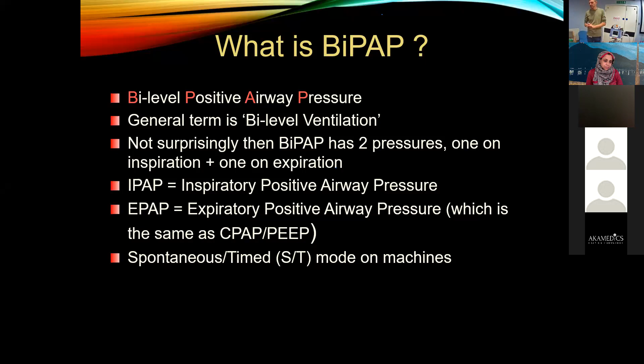So how does it work? The inspiratory phase pressure is triggered by the machine detecting your patient's inspiratory effort, okay? And in most of these devices, it's detected by approximately 6 mils of inspired air, okay? The machine will then start to deliver its inspiratory phase pressure, so IPAP, okay, providing assistance for your patient during their inspiratory phase, okay? The machines then alternate between IPAP and EPAP, synchronizing with the patient's own inspiratory and expiratory phases.